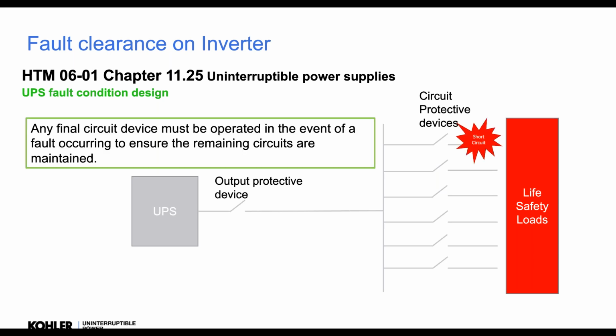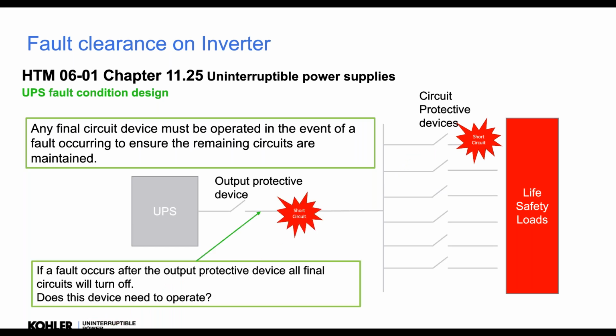Yeah, if you have a fault there, you don't want everything tripping. You don't want the UPS going off. You want everything else still to run. So the device must trip. Okay. But it does say every output device needs to go. So if you have a short circuit here, what is the point of this actually tripping? Because if this trips, you lose everything. All right. So sometimes you might say, well, I don't need that to trip, or I might not even need that device at all.